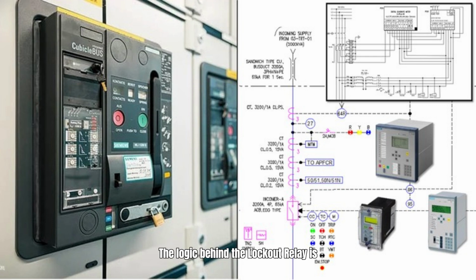The logic behind the lockout relay is straightforward yet critically effective. A trip signal originating from a protection relay activates the lockout relay, designated as 86, which in turn sends trip commands to multiple circuit breakers, such as CB1, CB2, and CB3, ensuring comprehensive isolation of the faulted area. To restore operation, a manual reset input is required directly on the lockout relay, emphasizing the deliberate design to mandate human intervention before any re-energization occurs.